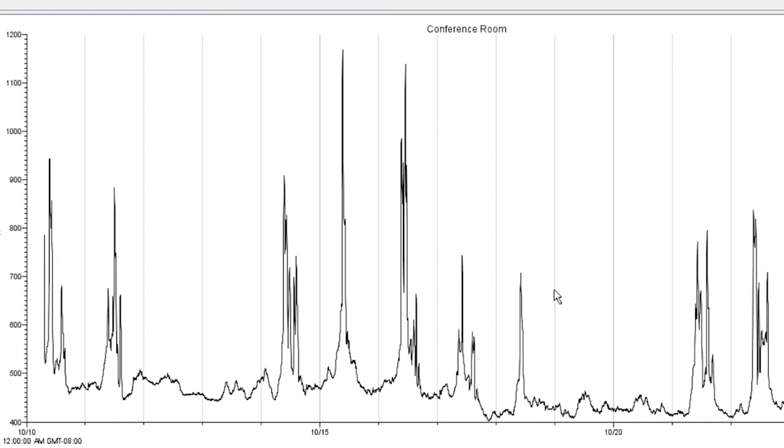Now, it's also a good idea to take measurements in each zone of a specific air handler to get a clear picture and to see if there are any anomalies that can help you diagnose issues with certain zones, for example. So this is the first step in doing an indoor air quality investigation, but this can give you an idea of whether you're overventilating or underventilating or whether you're in a good place.